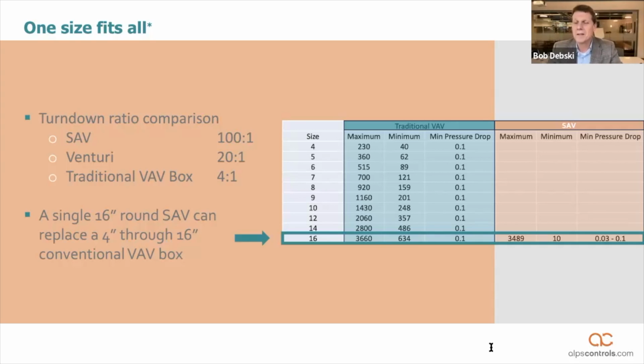So what does that mean in the real world? If you look at that graph on the bottom right, it means that one 16-inch smart air valve can replace 10 sizes of conventional air valves. It has the same airflow from a maximum of 3,500 all the way down to 10. It replaces them all. So what does that mean to you? That means that you have significant efficiency in design. You specify one box that can cover all 10 sizes. Now, keep in mind, we understand that there are certain construction challenges, whether that's beams that are in the way, duct work, conduits that can require a smaller duct. Guess what? You can still get the smart air valve in smaller sizes to accommodate those construction restrictions.